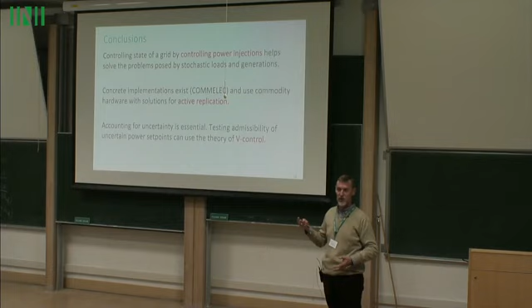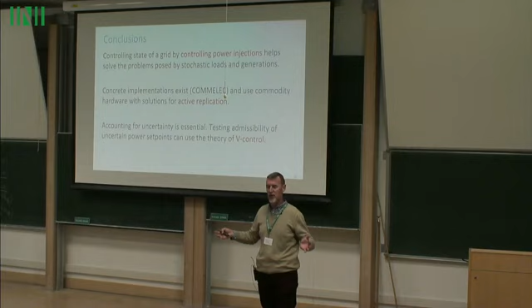What I've shown here is the microgrid, which is low voltage, 1000 volts. We're working on deploying it at the campus level, where the entire campus has every building as one microgrid, and then a medium voltage grid agent sees a number of low voltage grid agents, which for it are resource agents. At least at two levels we know how to do it. I'm not claiming we could run continental Europe with this, but certainly we can run a fairly large distribution network with this technology.